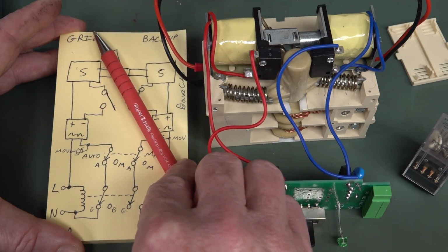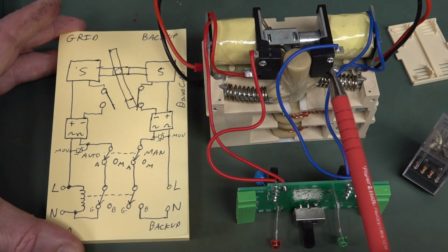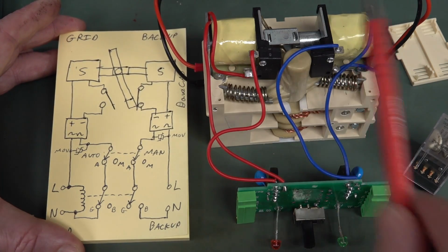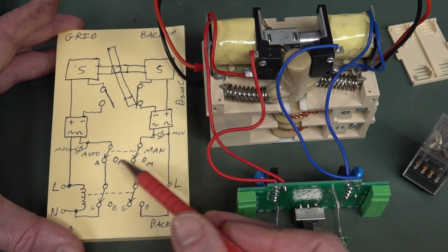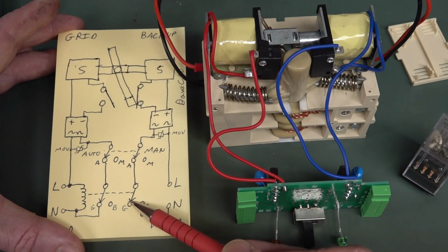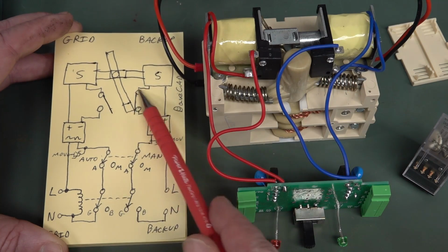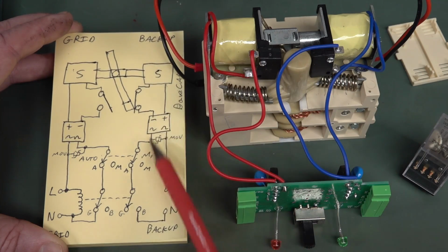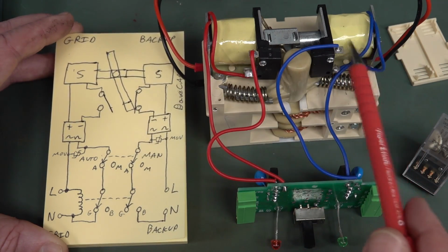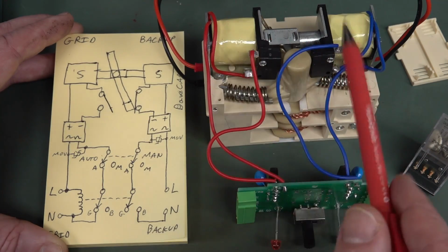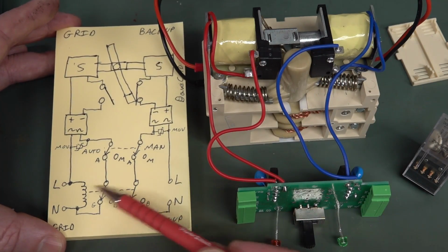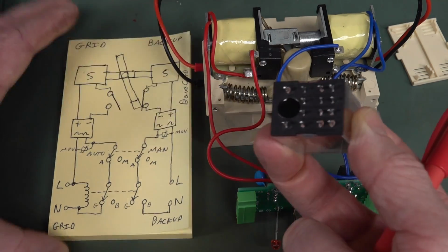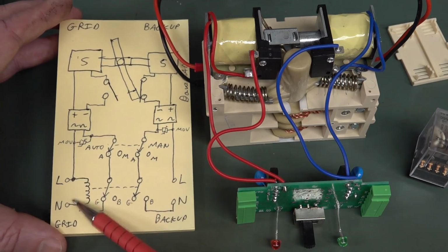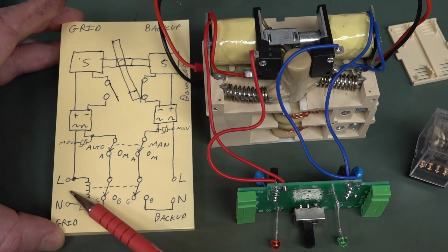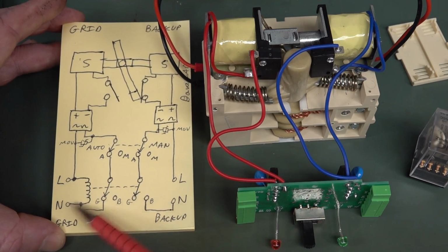With the armature in the grid position like this, it's going to actually close the micro switch for the backup solenoid over here. So I've put all of these switches in the current grid position, so the backup micro switch is enabled. The backup solenoid here is sitting ready to be engaged. But neither of these, during static operation, when it's not switching, are energized. So this is actually quite clever. Stick with me. Now, the relay coil, these 2 pins here, they're actually connected across the grid side. This is why the grid side is the priority side. So you want your priority source to be connected to the relay.